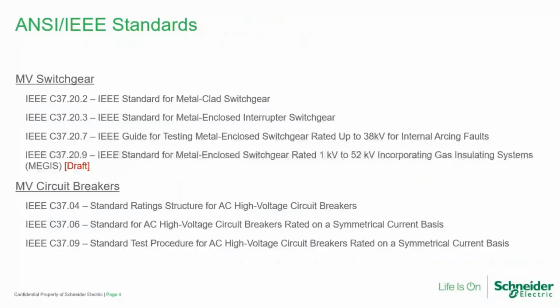Now, I think it's always important to talk about codes and standards a little bit, and where we are with the IEEE codes and IEEE ANSI style codes. Currently today, the most prevalent two codes in medium voltage switchgear are the C37.20.2 and C37.20.3, and these are codes that govern the recommended ratings, the testing standards, and the construction standards specifically around metal-clad switchgear and metal enclosed switchgear, respectively.